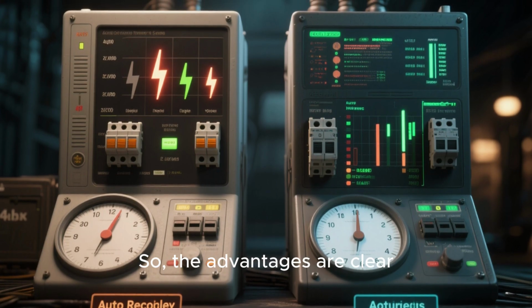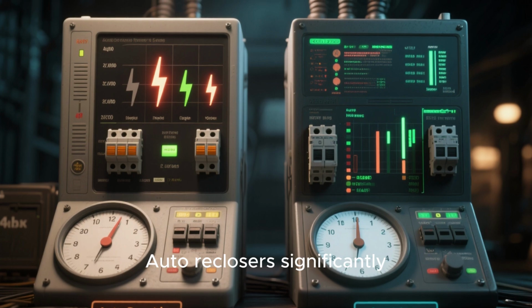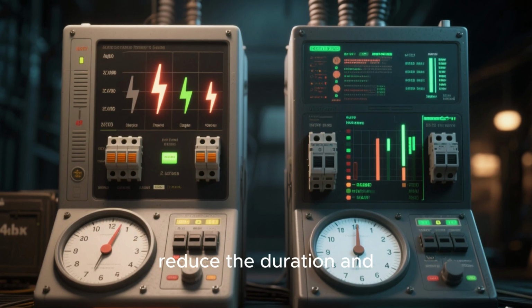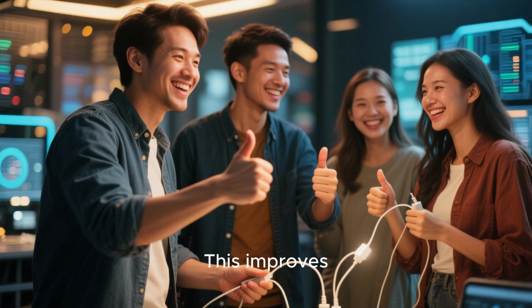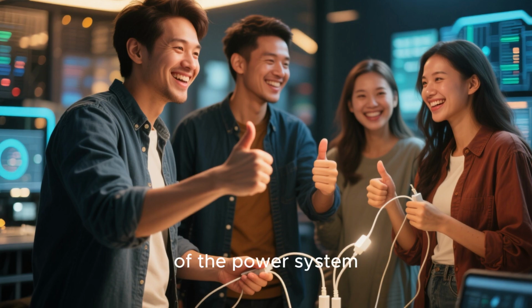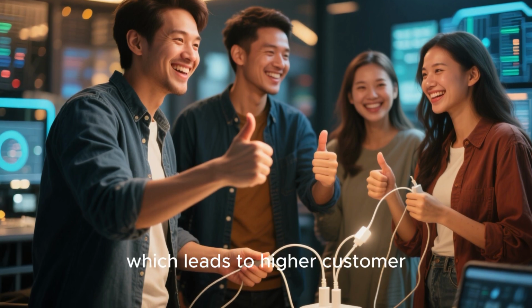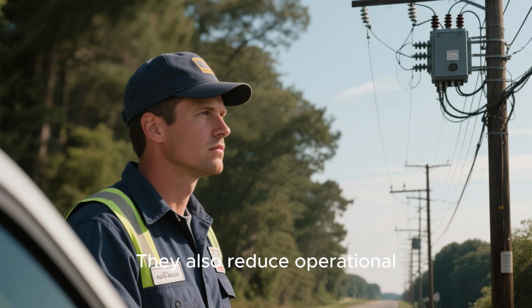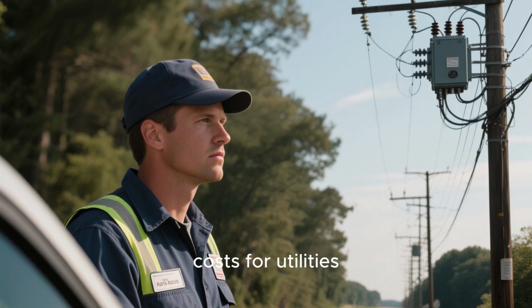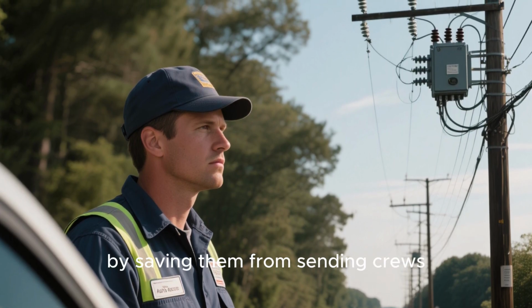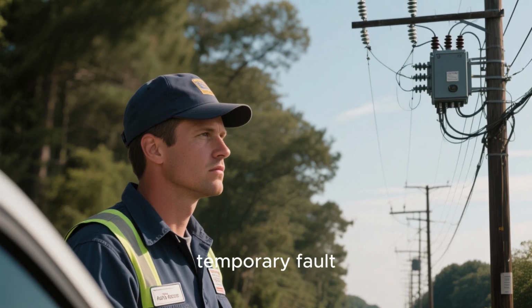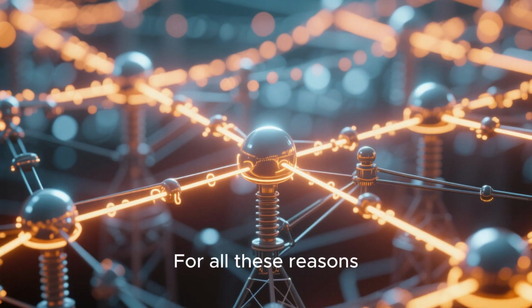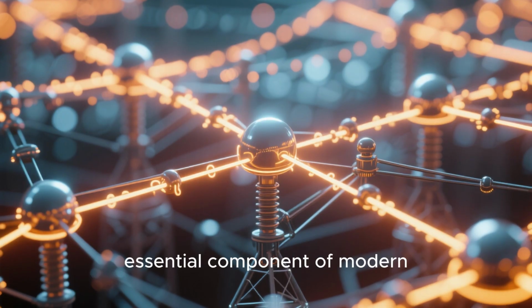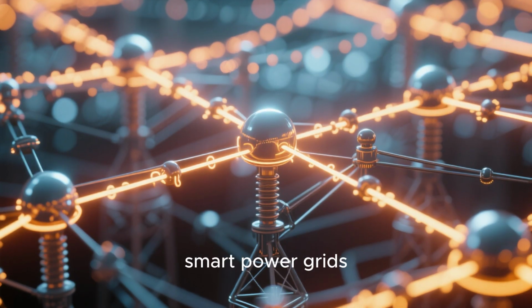So, the advantages are clear. Auto reclosers significantly reduce the duration and frequency of power outages. This improves the overall reliability of the power system, which leads to higher customer satisfaction. They also reduce operational costs for utilities by saving them from sending crews out for every minor, temporary fault. For all these reasons, they are an absolutely essential component of modern, smart power grids.